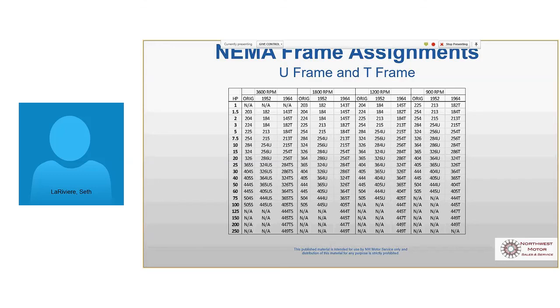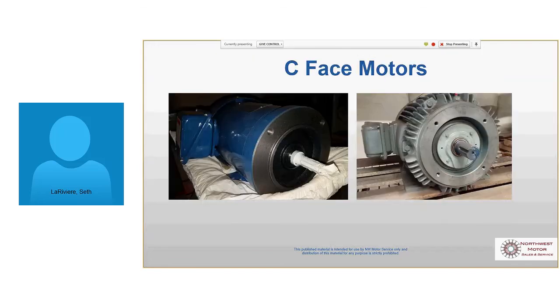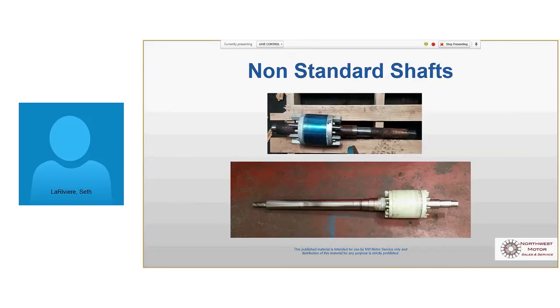So we talked a little earlier about those frame suffixes, like 254TC, this is a C face. Commonly that'll go up to a gearbox or a pump or any driven equipment. This is an example of some non-standard shafts. Obviously this one's got a bunch of steps in it. There's a variety, of course, of custom applications. This is a JM or a JP close-coupled pump motor. You see it's got a step here in the shaft, and it's also got a threaded hole here for the pump impeller to go on.